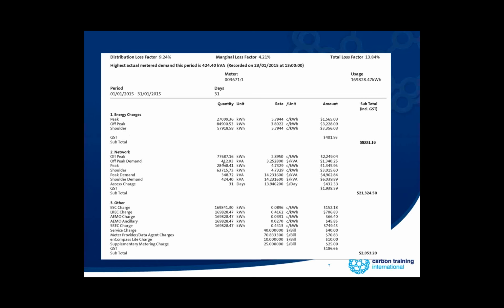Say if we had a 400 kilowatt pump, or 4 100 kilowatt pumps running, the monthly charge for demand, if we kept all our pumping in off-peak periods, would be $1,340 a month instead of this combined. If we pumped whenever we felt like it, we'd be charged close to $11,000 a month.